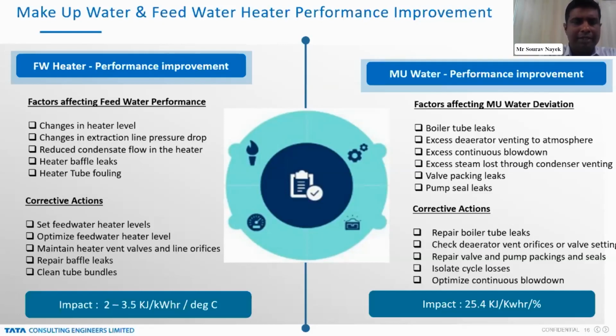Now, as corrective actions, we should always run our control loop in a very efficient manner, so that we can maintain the feed water heater level. Our vent valves and orifice can be optimized so that we minimize our losses. The baffle leaks should be repaired periodically, and the tube bundles also should be cleaned during the annual shutdown period, or whenever it is needed. We can bypass and do the cleaning of these tube bundles.